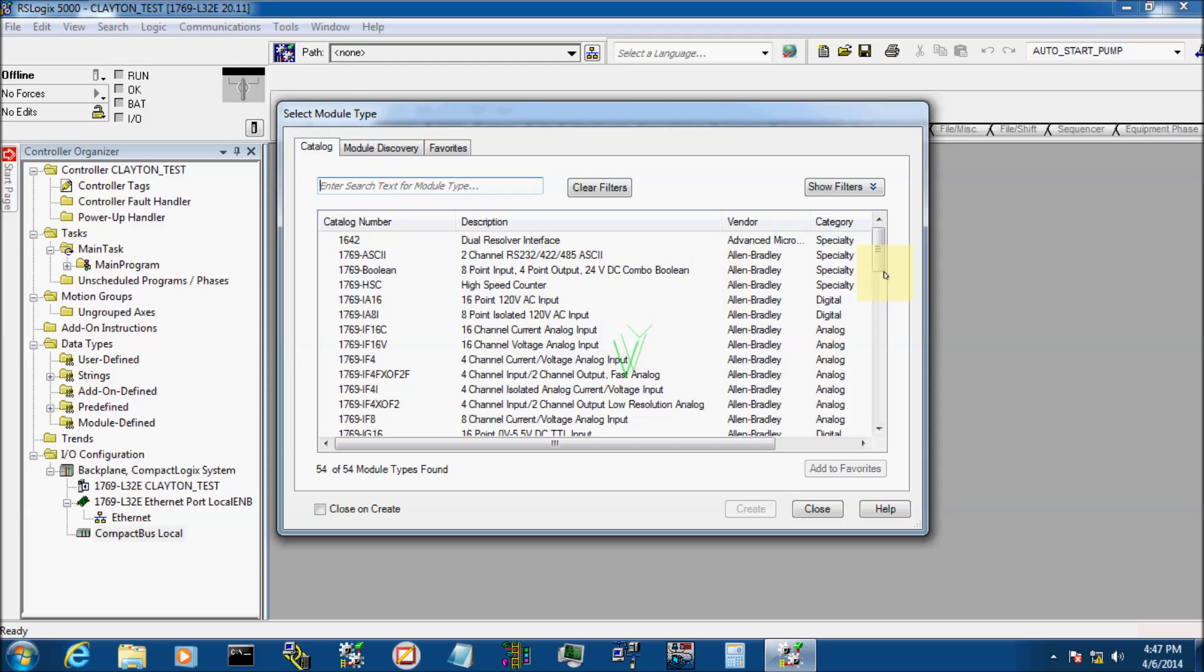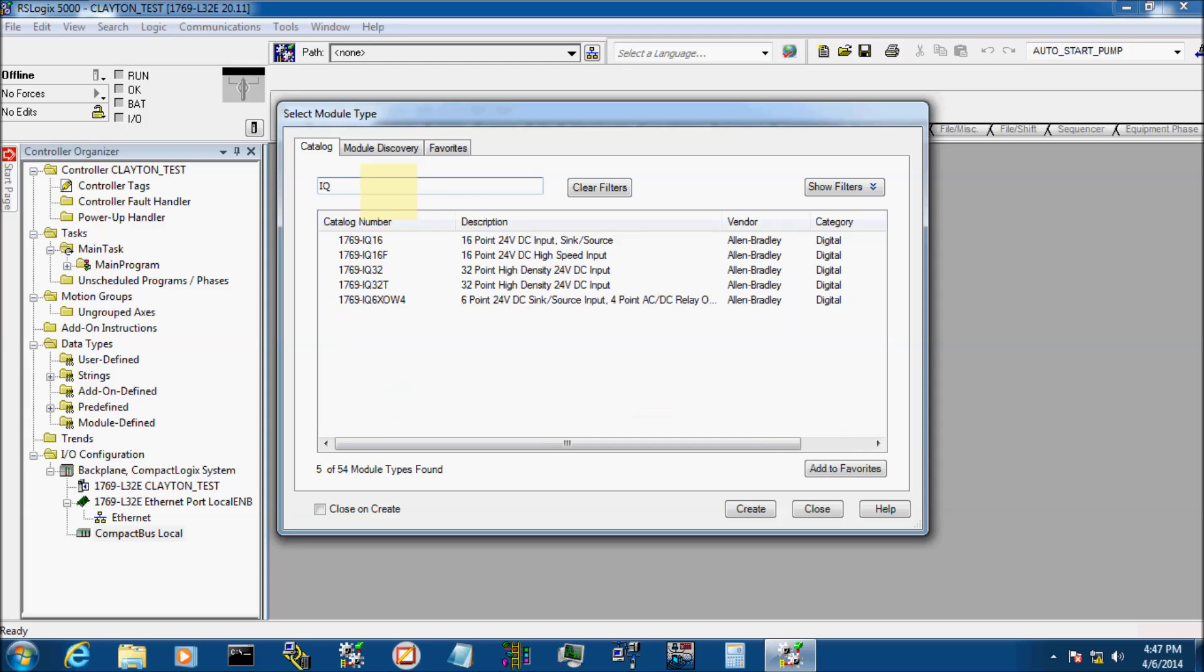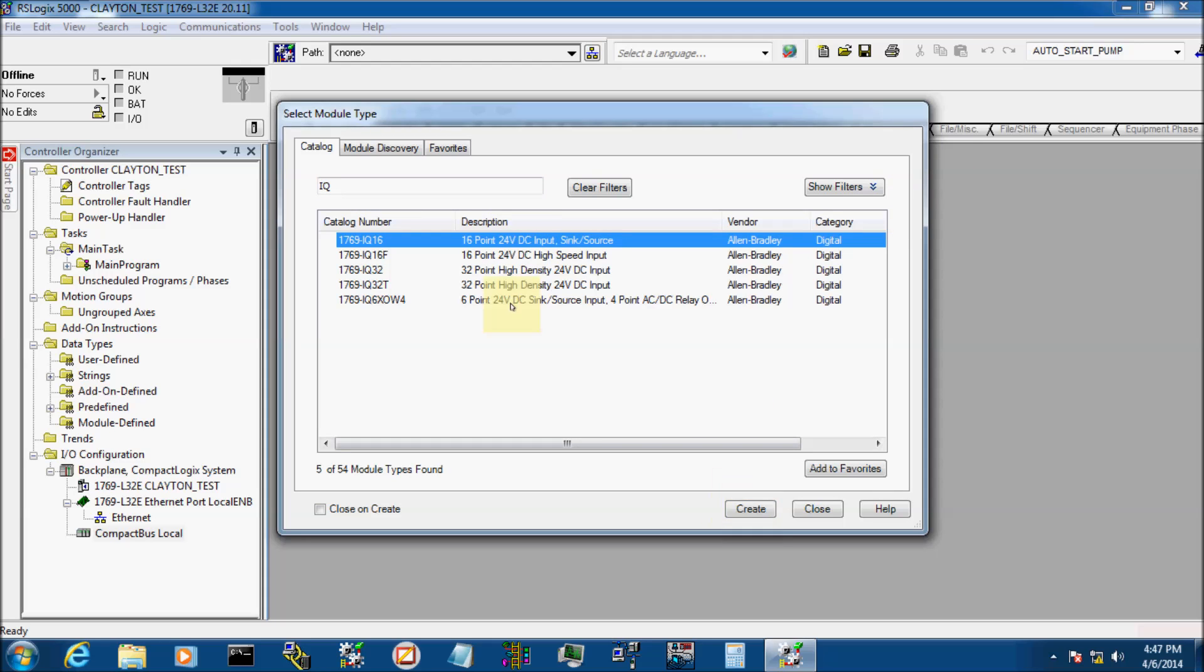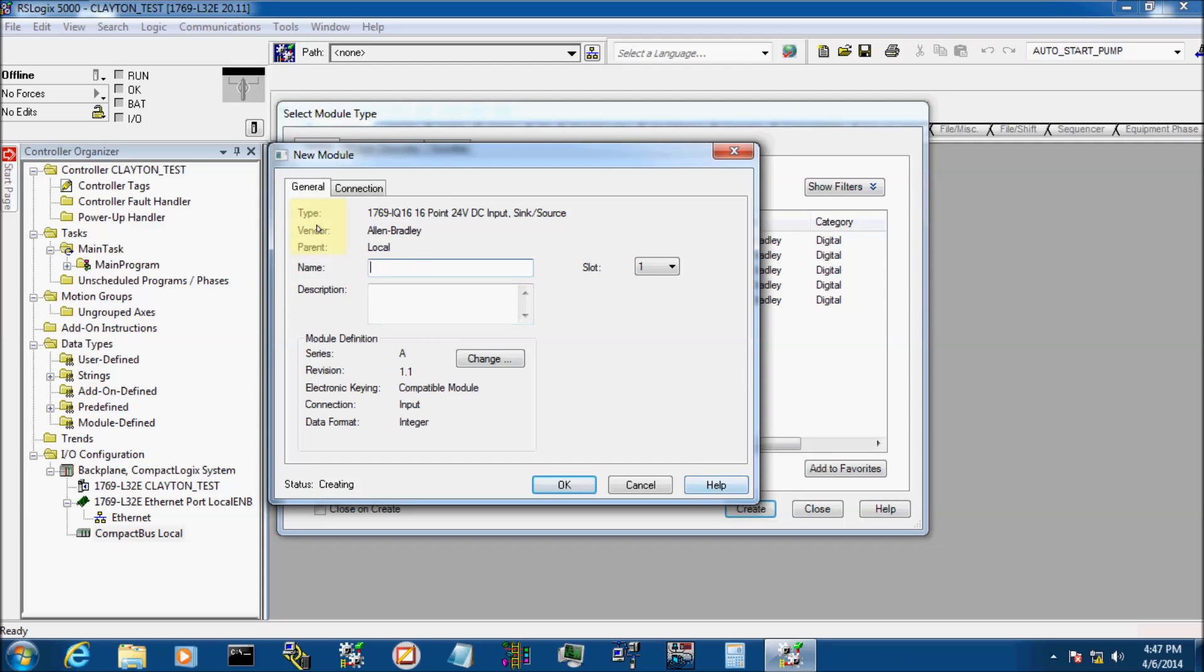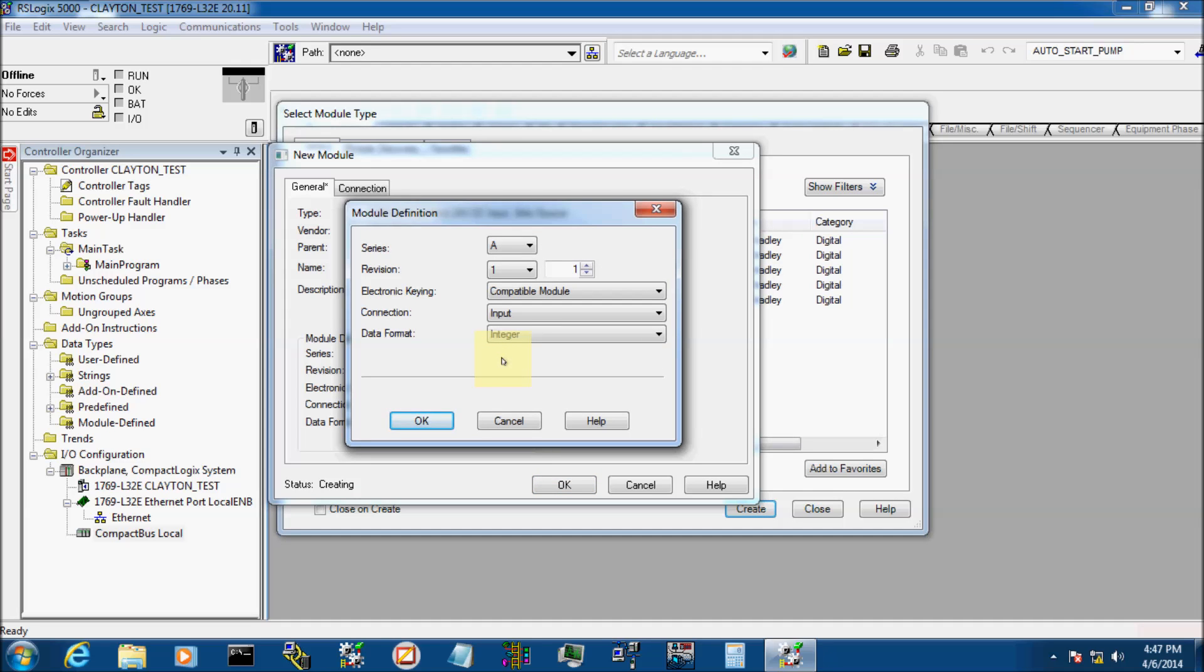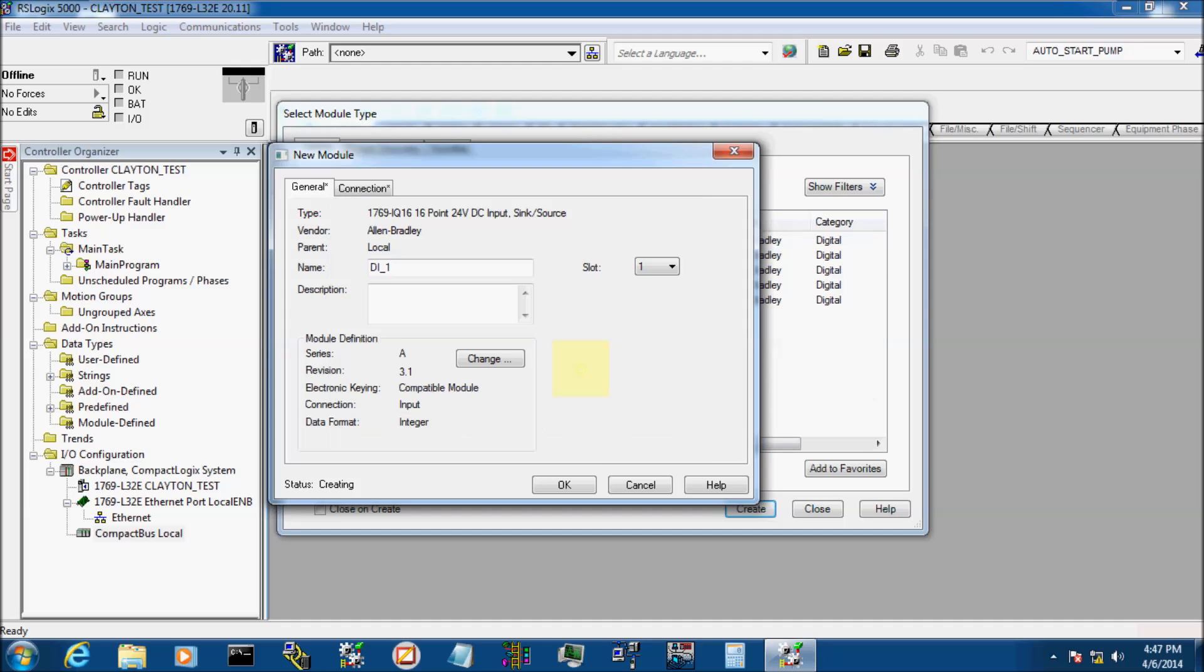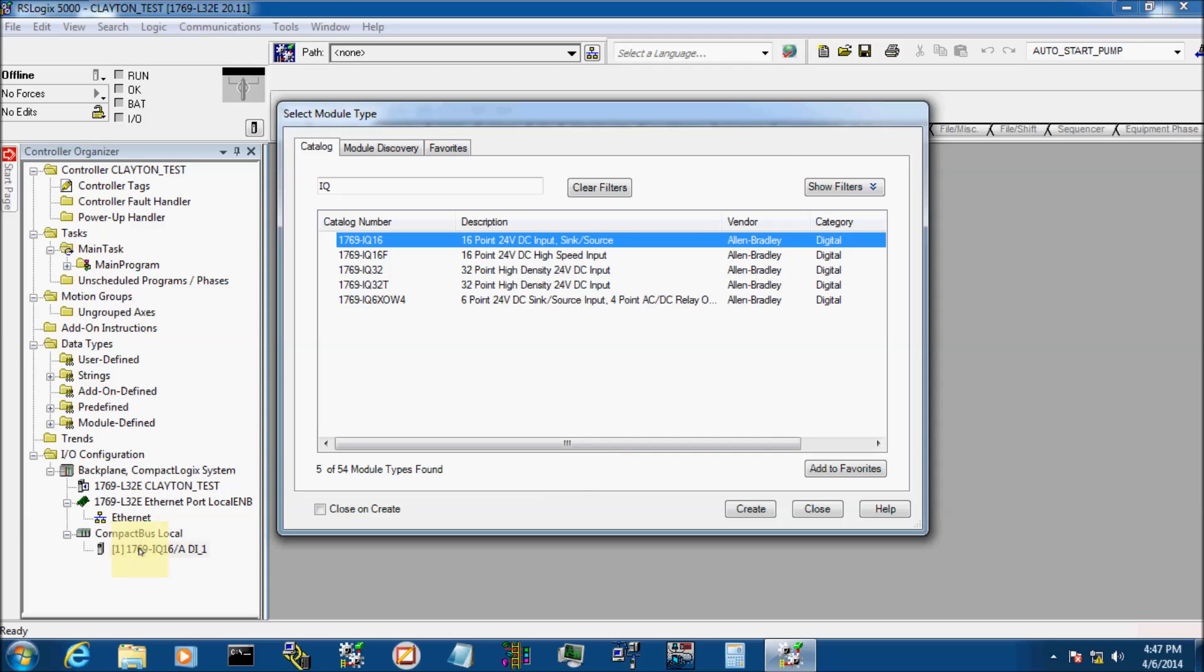So here's all the possible cards Allen Bradley makes for the Compact Logic. We're going to just go ahead and type in up here. I've got a IQ 16, right here. Go ahead and hit Create. It's a 16-point DI card, 24-volt DI card. Name. We're going to go ahead and name it DI-1. It's in slot 1. Right here, the Series and Revision. We need to change that because each card has its own firmware on it. You have to look on the card to see what firmware it is. The card I have is actually Major Revision 3.1. So we're going to click OK. And if you see down here, now it's added that card on my bus.